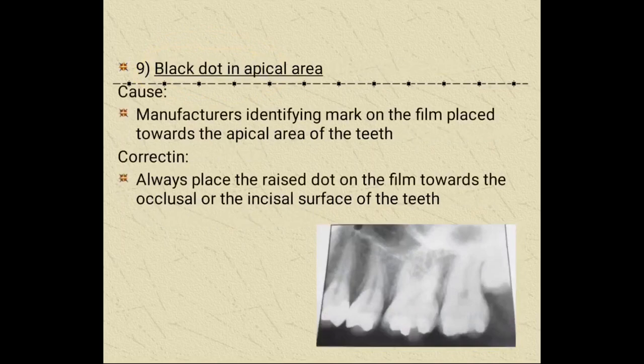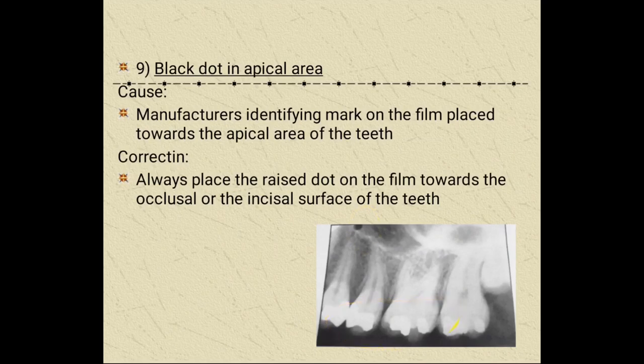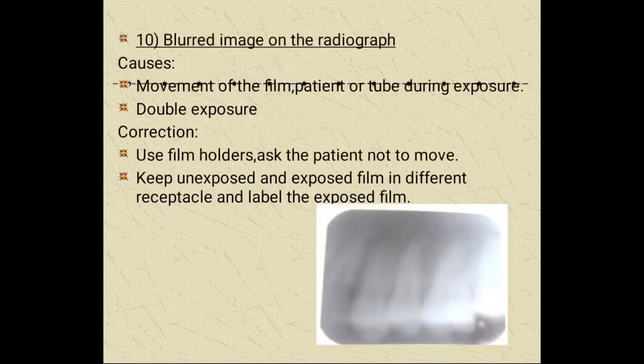A black dot in the apical area is due to the manufacturer's identifying mark on the film being placed towards the apical area of the teeth. Always place the raised dot of the film towards the occlusal or incisal surface of the teeth. A blurred image on the radiograph is due to movement of the film, patient, or tube during exposure, or a double exposure. Always use film holders, ask the patient not to move, and keep unexposed and exposed films in different, labeled receptacles.